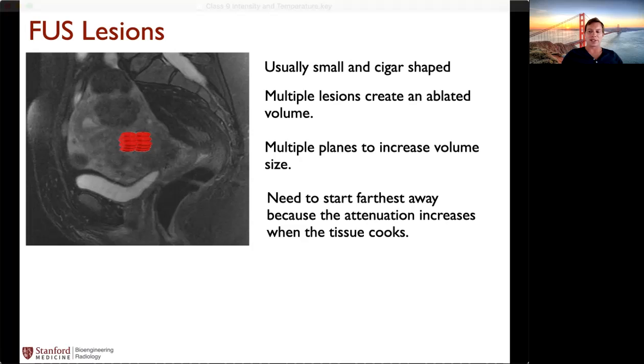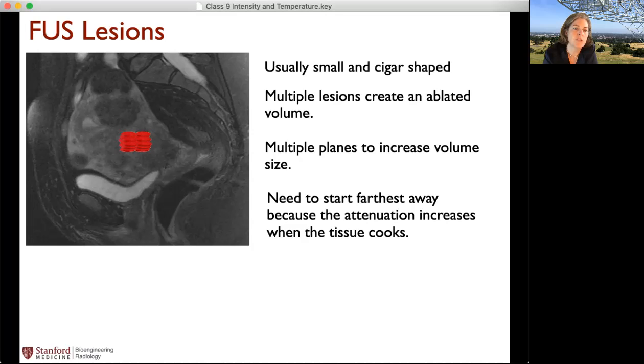And Kim, you mentioned 20 seconds for each of these ablation areas. What's stopping us from using higher intensities for shorter periods, just to make it faster in case the patient's moving? If you could do a really quick scan. Yeah, that's a good question. So there's certainly the power output on the transducer. And then, going for a longer time period is an easier way to get more energy in. That's probably the main reason.